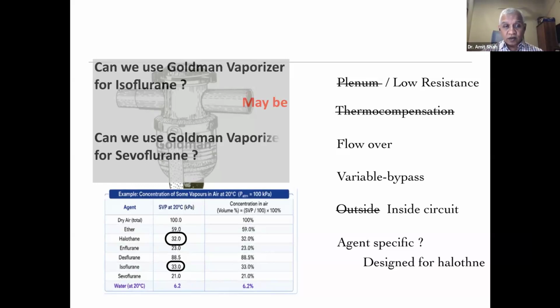Can we use sevoflurane? Some of them actually put sevoflurane into it. The vapor pressure is very low and the concentration requirement is very high. You cannot use sevoflurane in a Goldman vaporizer. Very simple reason, because the vapor pressure is different and quite low compared to halothane and isoflurane.